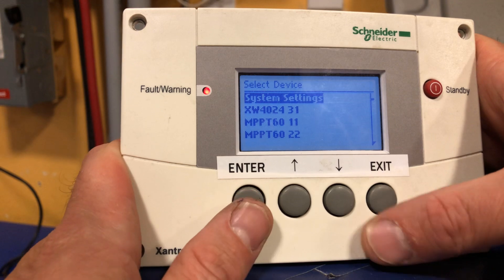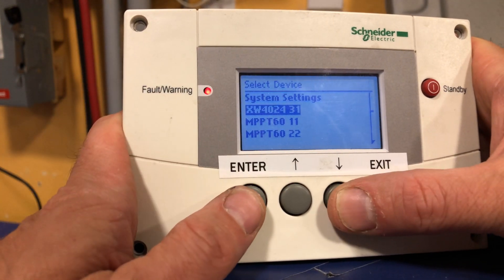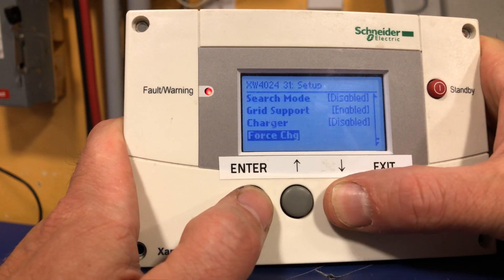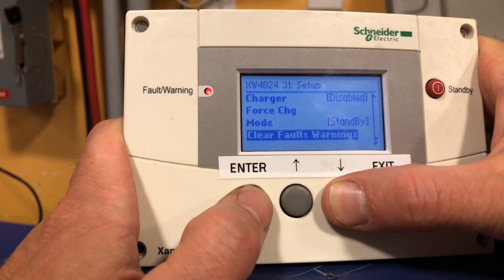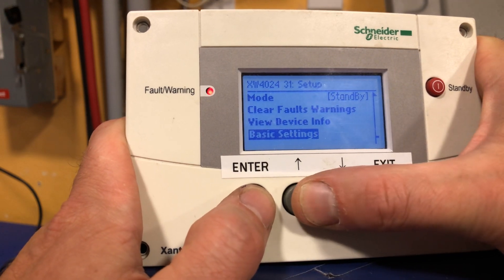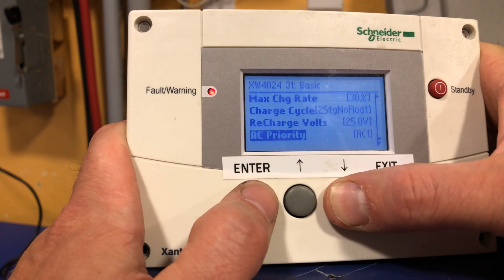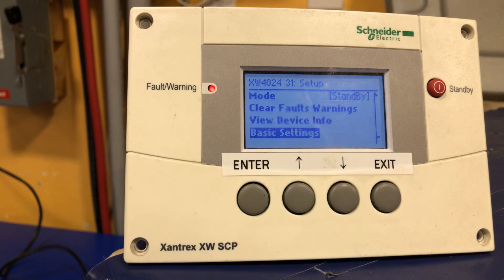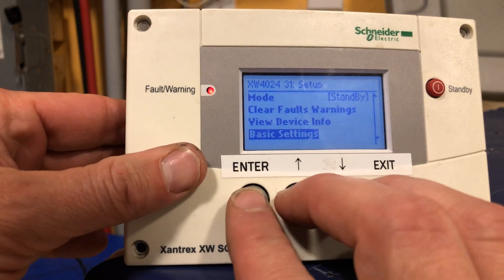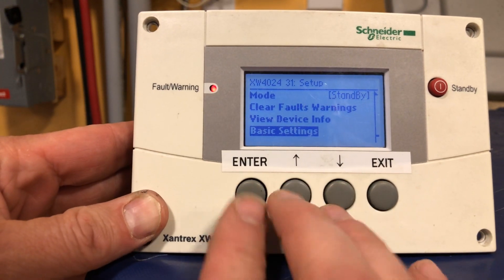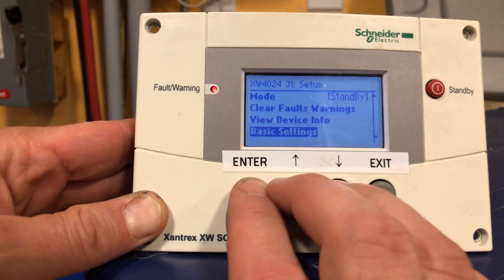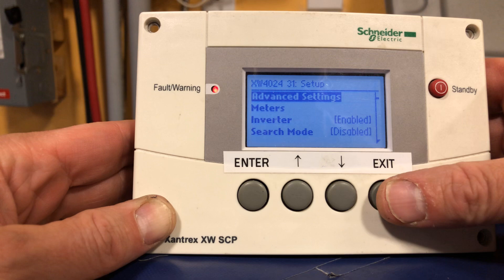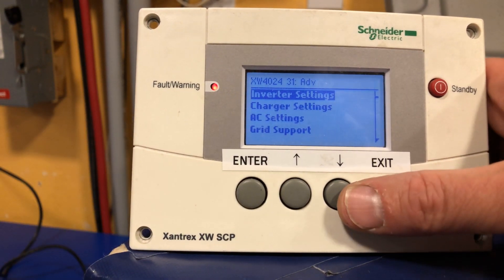I'll go back, exit to the device menu, press down to select the XW inverter, and press enter. Let's go under basic settings. To access the unique identifier we have to press enter, up, and down simultaneously — so I'm going to button-mash three at a time. And when I press them at exactly the same time the advanced settings pops up. Press enter.